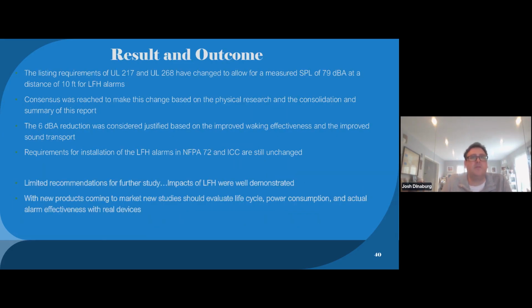So what happened? We did all this research in 2020. We actually changed the listing requirements for 217, 268. The consensus agreement of that technical panel was that a 6 dBA reduction from 85 to 79 was justified based on all this data and the research that had been done, without doing additional work. So now low frequency alarms can use, that's 1/4 the power at 6 decibels reduction. So it's a lot less power requirement on those devices for the batteries and for the sounders. So the intent here was to make something technologically tenable for manufacturers.